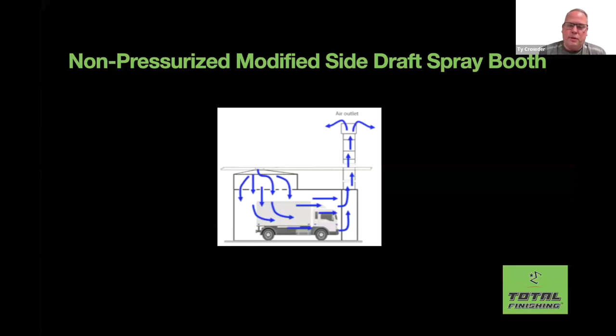This is going to leave a huge, almost a 45-degree angle void at the front left. I don't really have a mouse that I can draw on here, but if you were to look at the bottom left half of that and draw a line at a 45 degree, you'd have a complete dead zone where there's almost no air movement.